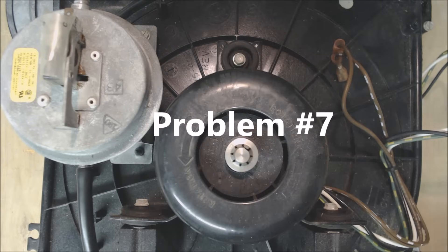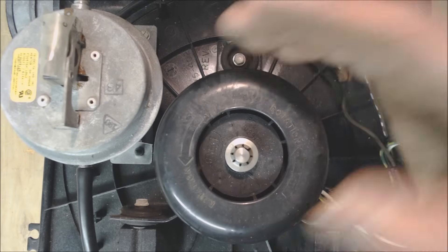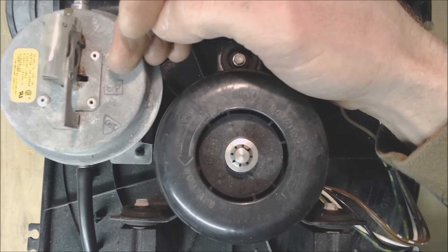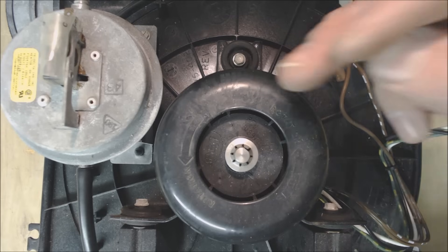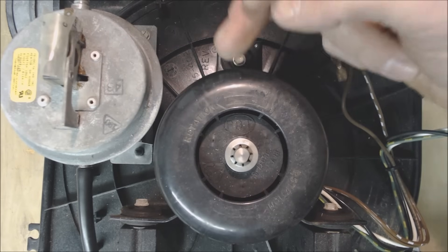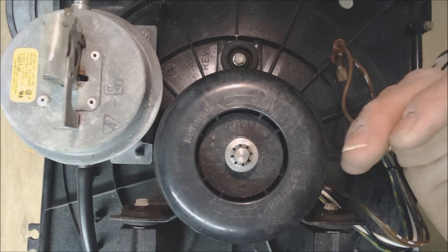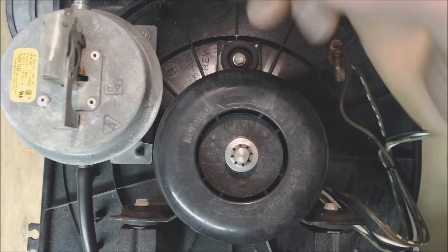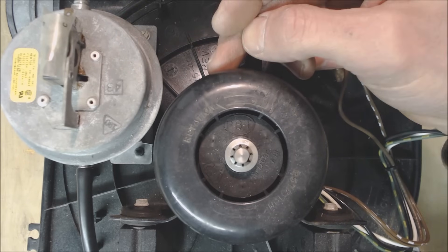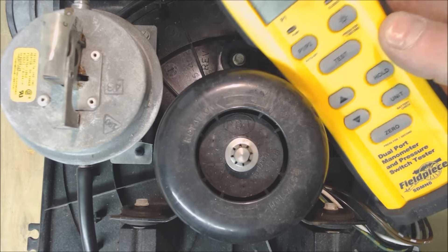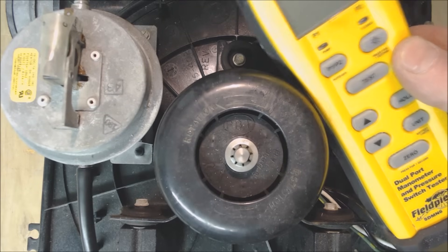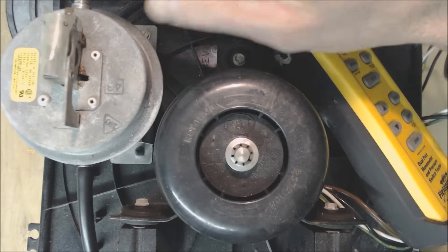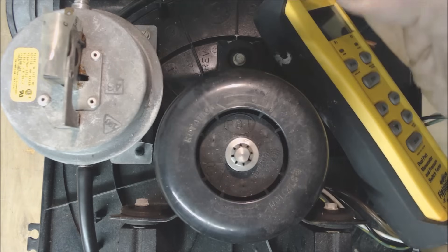So problem number seven could be that the inducer motor actually is running but you're having some problem with proving that this is running with the pressure switch. So the sequence of operation for heat goes with the inducer motor turning on first, the pressure switch proving that the inducer motor is working and that there's no clogs and then after that the ignition source gets turned on. And what could be happening is this pressure switch could not be proving that this is operating and I like to typically measure the pressure switch out with the SDMN6. So this tool right here is very useful because you can actually isolate the pressure switch completely away from the system just to make sure that this is correct or not correct.